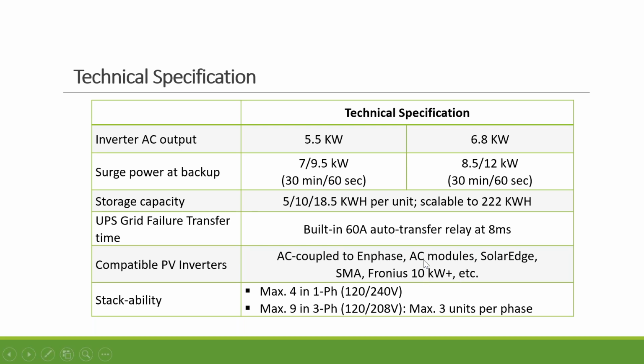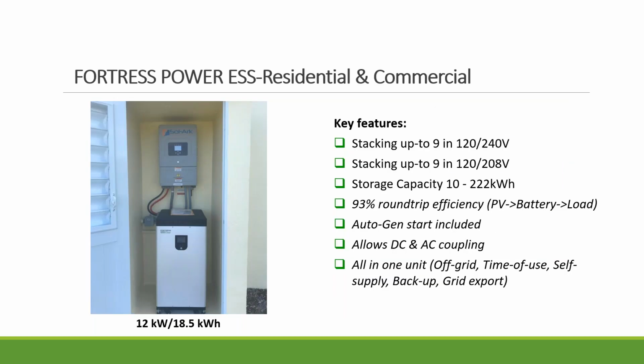Those are inverters it can AC couple to. Like I mentioned, you can do single or three-phase. In three-phase, you have 3 legs, and on each leg you put either 1 inverter, or 2 or 3, for your 208 systems. Now, there's another newer inverter on the market that has the charge controller already built in.